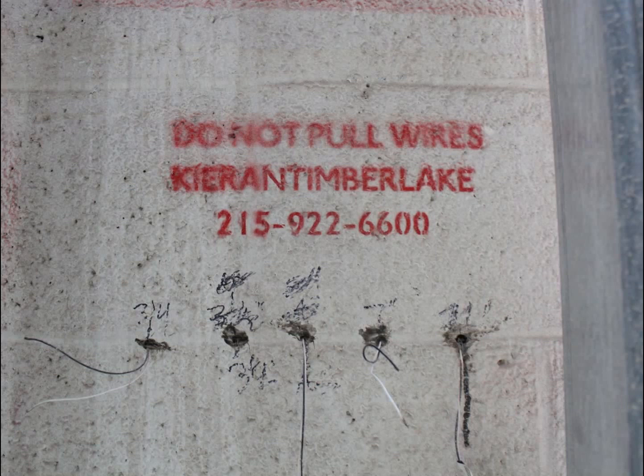But one of the things that we were actually discussing last night is the challenge associated with having this absolute layer cake, this wedding cake of different standards in your building. Some things are communicating on Wi-Fi. You might have your Lutron at 433. You might have other stuff that's running on 900 megahertz, and each thing requires its own little base station, its own little database that you have to be pulling from. For us, the real desire is to have as few of these different systems as possible, because all that adds complexity, maintenance, cost. So for us, it's one of the challenges that we feel, and we're hoping that perhaps with the very open, very well documented API, we can start to see other firms that can allow for that type of input into their systems.